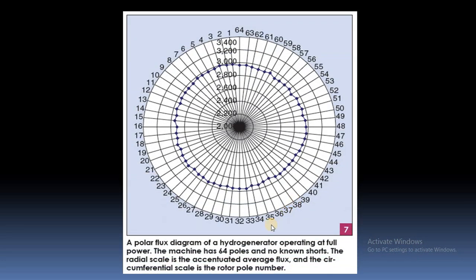Here we can see a hydro generator operating at full power — the generator is synchronized and operating at full power. This machine has 64 number of poles, and by using this online technique we can determine which pole has shorted turns. From this plot, there is no significant deviation of the magnetic flux density, so no known shorts are found. The radial scale shows average flux from 2000 to 2600, and these are the pole numbers from 1 to 64 — the average flux is almost the same for each pole.